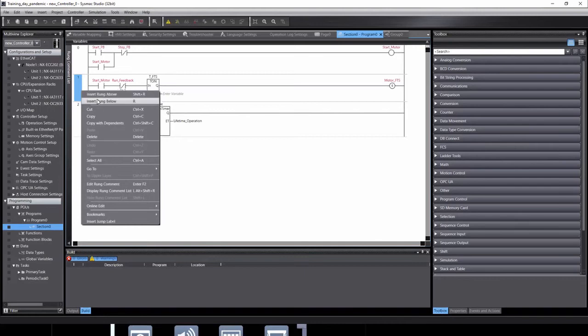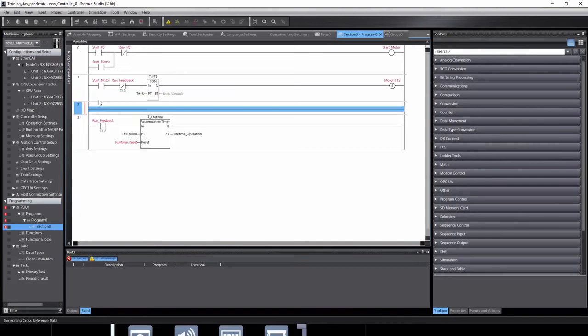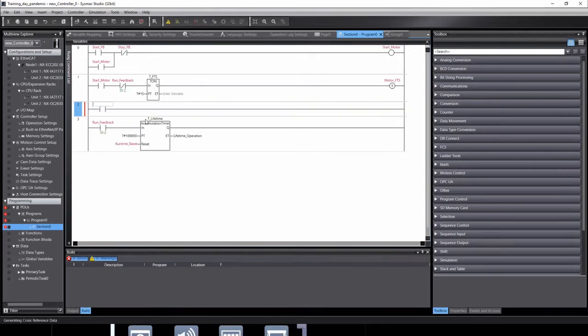So I'm going to add a rung below the fail to start bit rung. And it's going to say, if we have the fail to start alarm, we aren't trying to start the motor, which would be this bit here. And we'll need to make a new bit here, an alarm reset, and we can use this over and over again in our code.